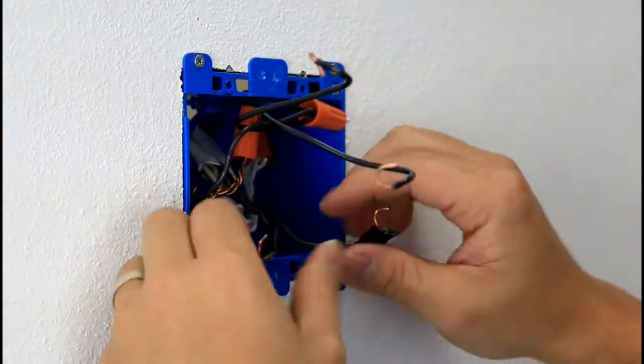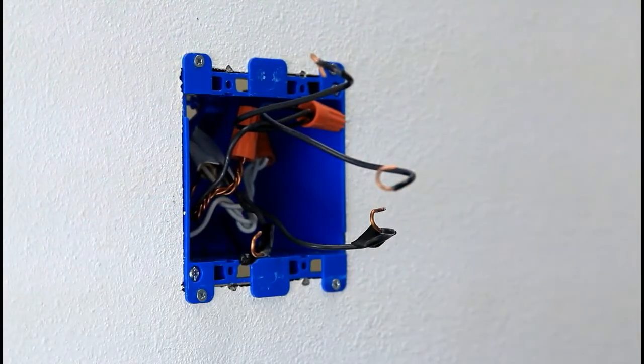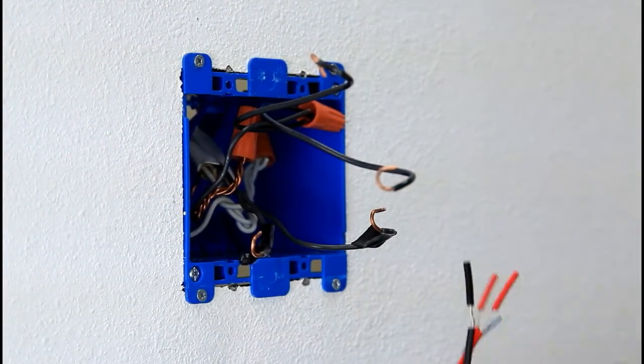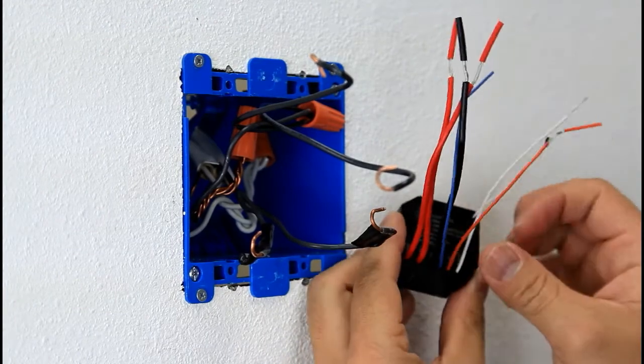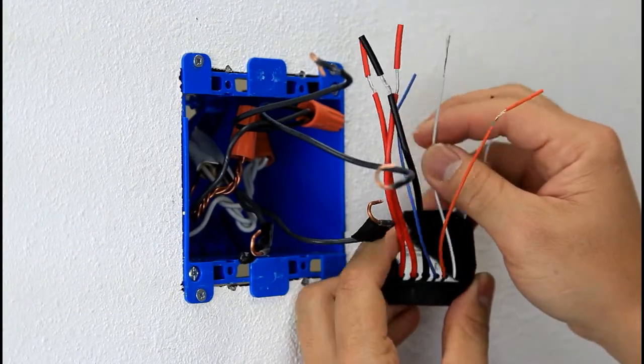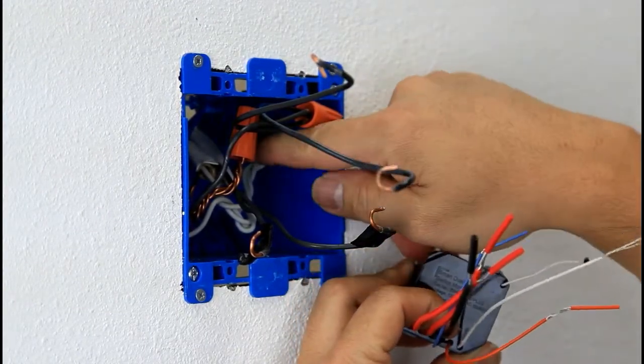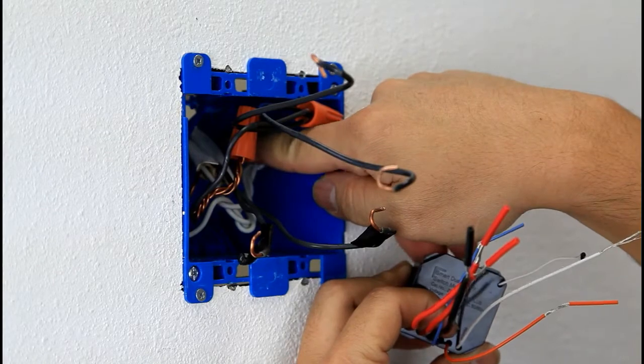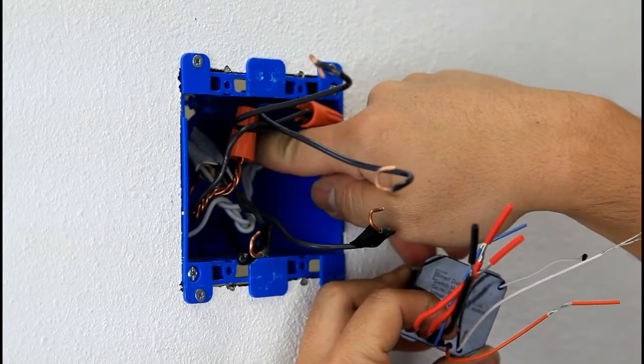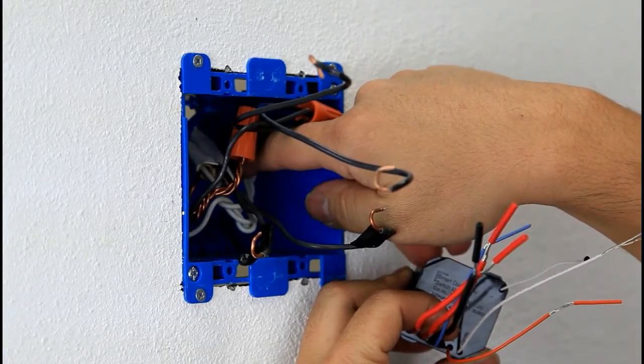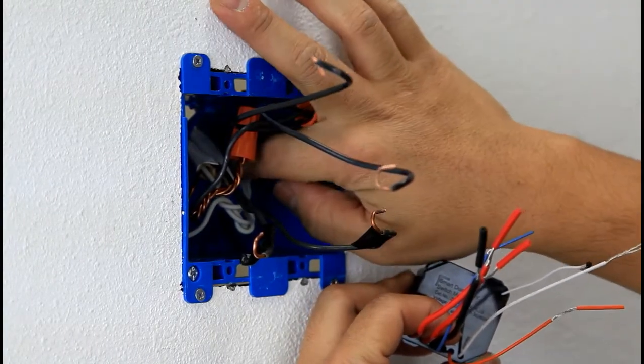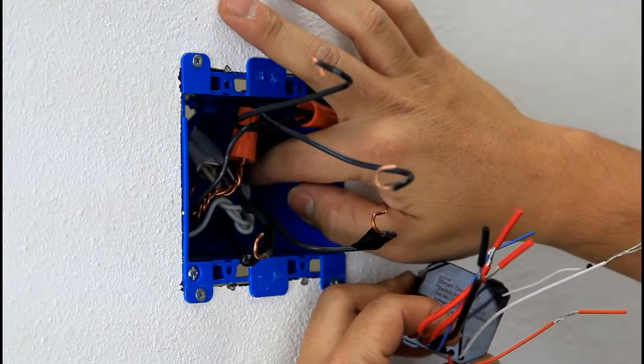And then this is your load. For the relay, you will need to have a neutral. Normally, the neutrals are in the back of your junction box. So you will have to actually go look further in the box and sometimes they're tucked in and hide back there.